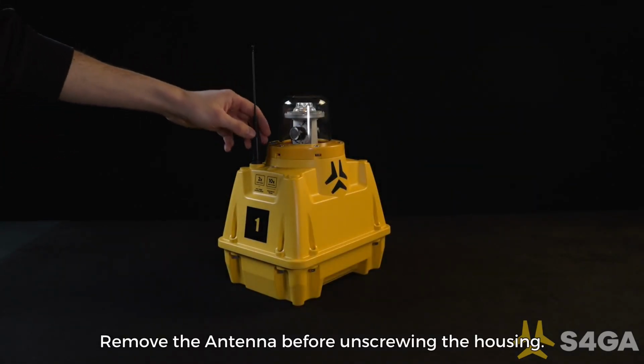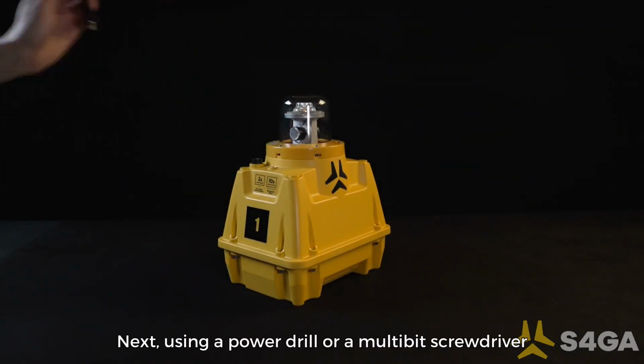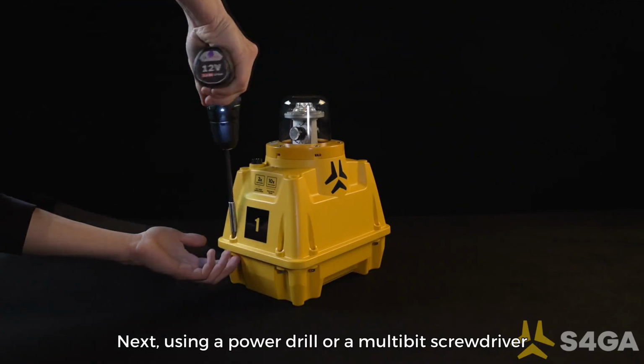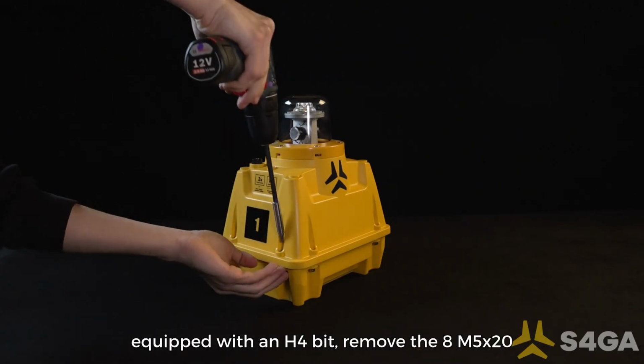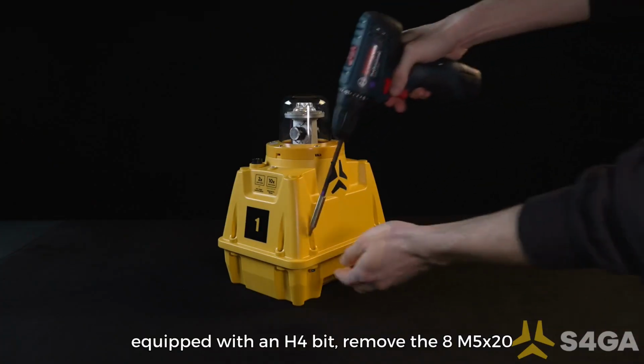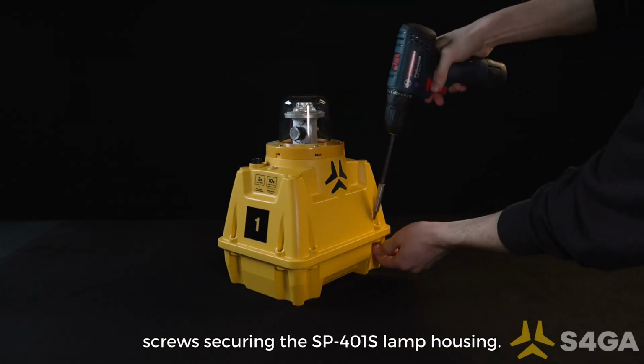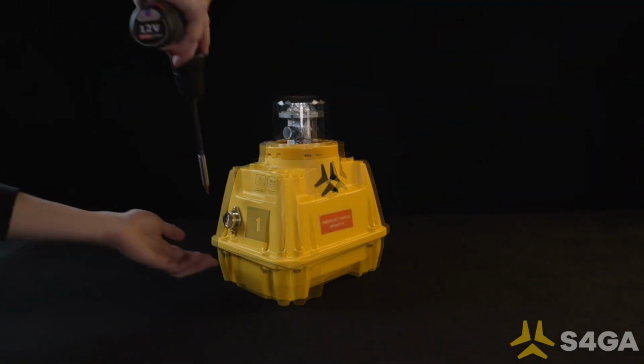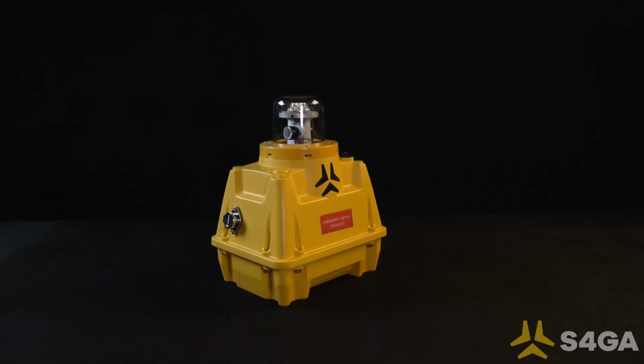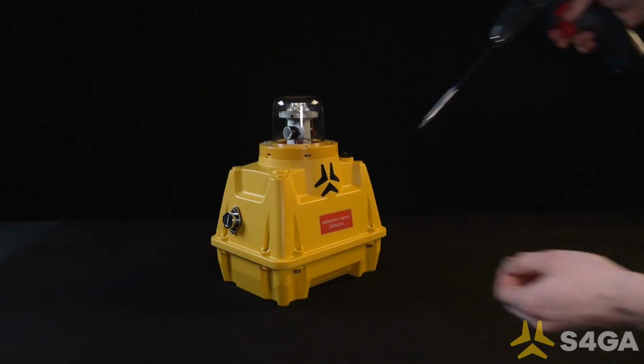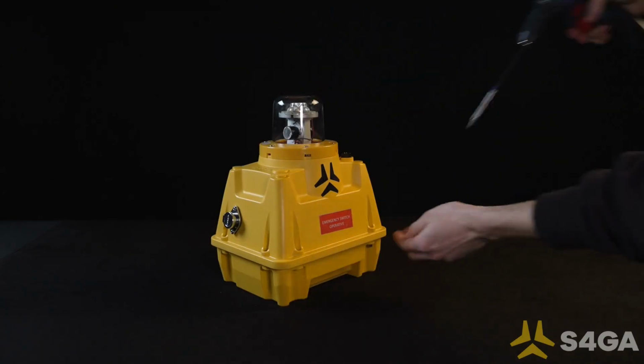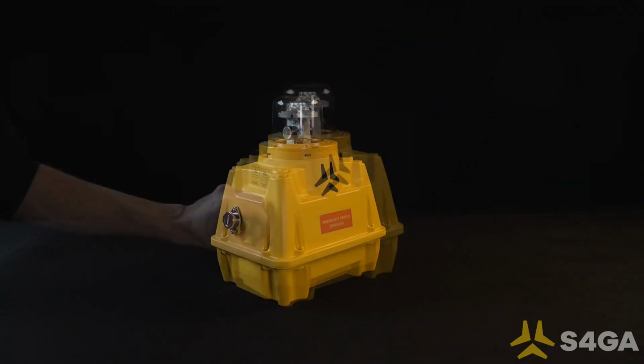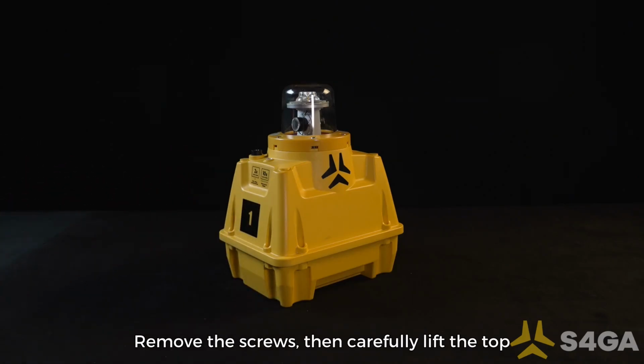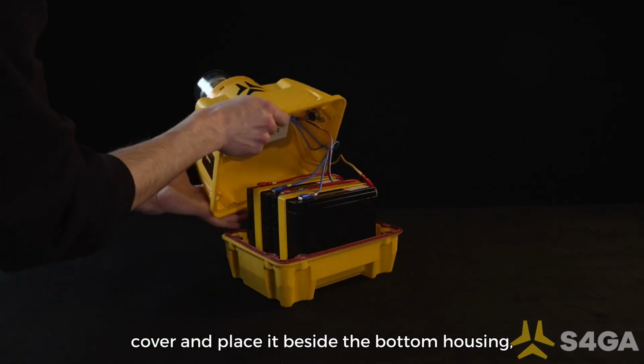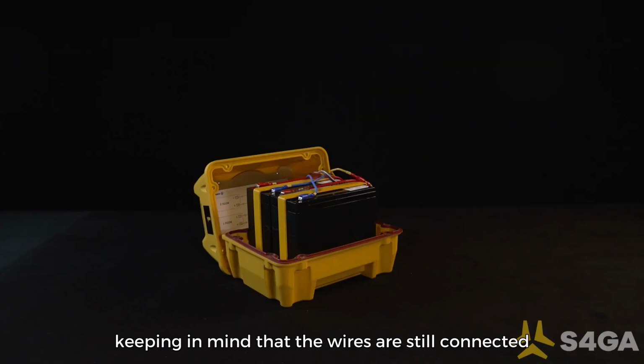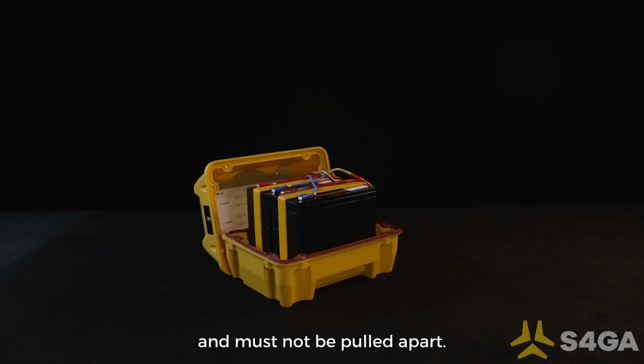Remove the antenna before unscrewing the housing. Next, using a power drill or a multi-bit screwdriver equipped with an H4 bit, remove the 8 M5x20 screws securing the SP-401S lamp housing. Remove the screws, then carefully lift the top cover and place it beside the bottom housing, keeping in mind that the wires are still connected and must not be pulled apart.